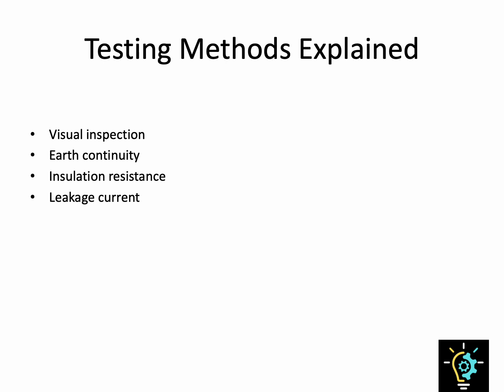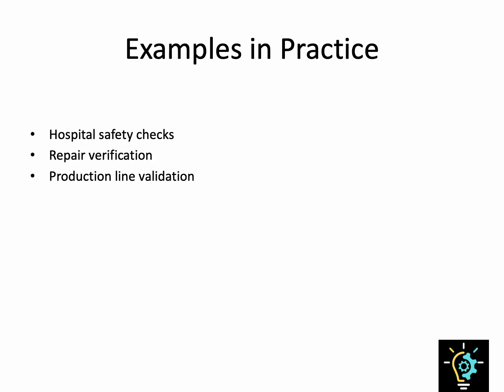The applied part leakage test checks that floating applied parts, like BF and CF types, remain safe for patients. The standard also allows different test methods: direct, differential, alternative. They're not as harsh as type tests, but they are robust enough to reveal when a device is unsafe. So what are these in real practice?